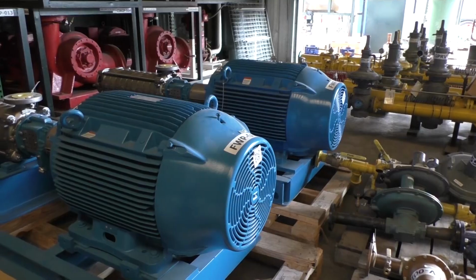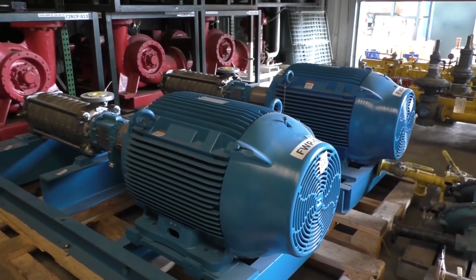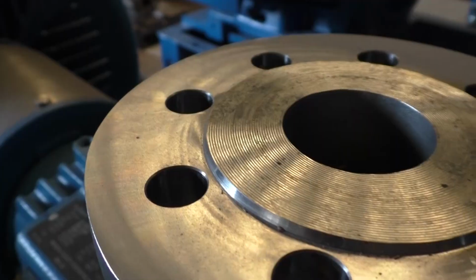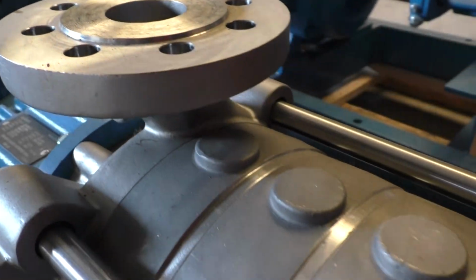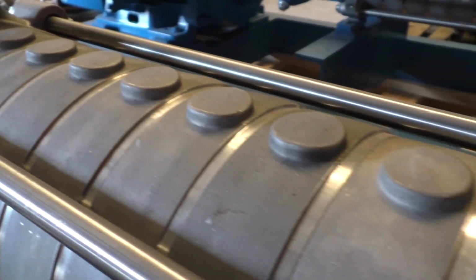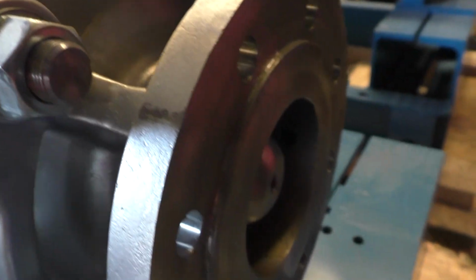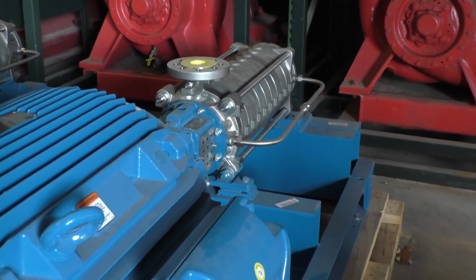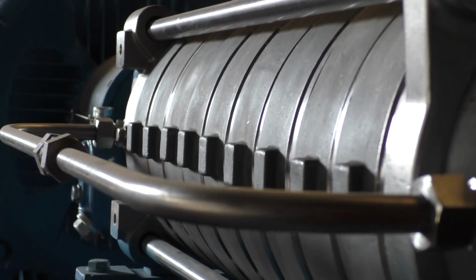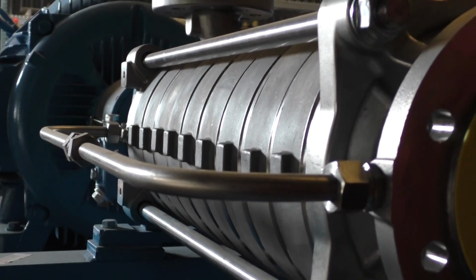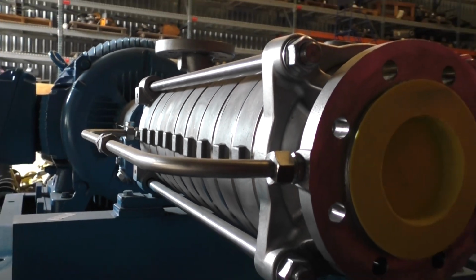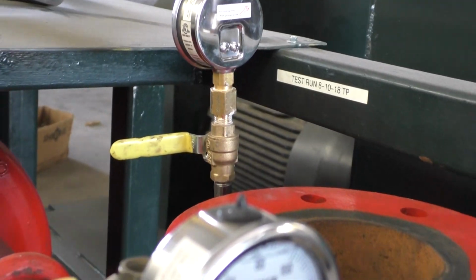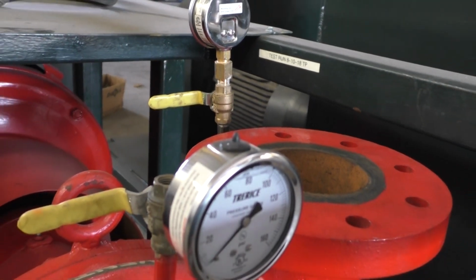So how do we avoid cavitation? The short answer is to ensure that our net positive suction head actual is greater than our net positive suction head required. In understanding these two terms, first understand that net positive suction head, or NPSH, is the liquid pressure existing at the suction end of the pump. Our net positive suction head actual, or NPSHA figure, is defined by what the system is actually producing, hence the reason it is imperative to have a pressure gauge at our suction side of our pump.